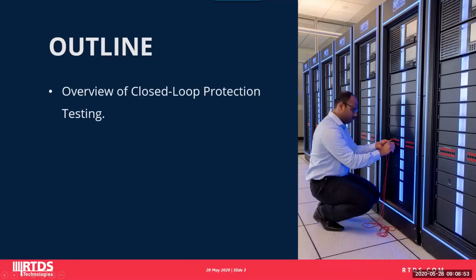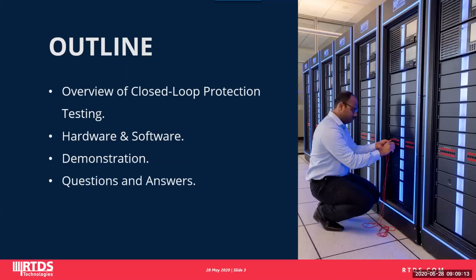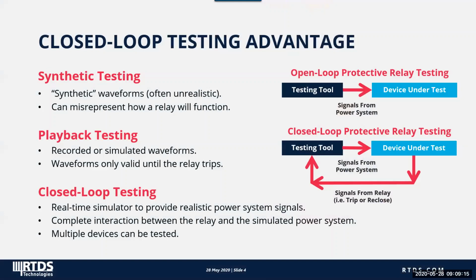We'll have a quick overview of closed loop protection testing using RTDS and a detailed look at the hardware and software features for such applications. We'll run a demo using a protective relay that supports both GOOSE and sample values for a line distance protection scenario, followed by the Q&A session. Without further ado, let's get started.